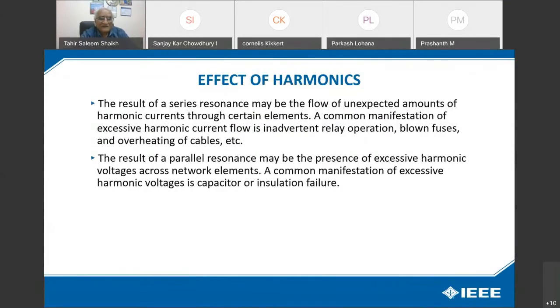The result of a series resonance may be the flow of an unexpected amount of harmonic current through certain elements. A common manifestation of the excessive harmonic current flow is inadvertent relay operation, blown fuses, and overheating of cables. The result of a parallel resonance may be the presence of excessive harmonic voltage across the network elements. A common manifestation of excessive harmonic voltage is capacitor or insulation failure.